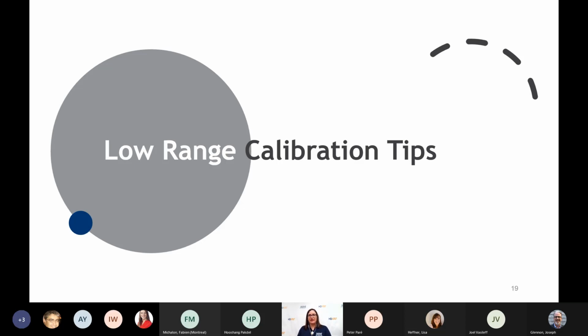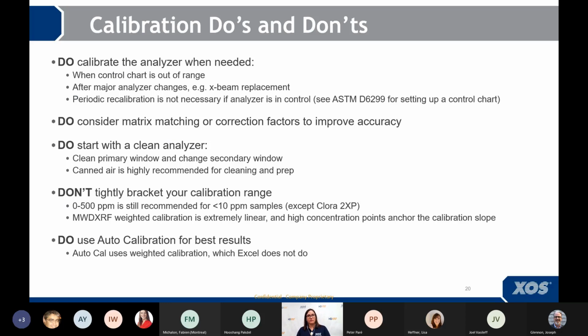First, we'll start off with our calibration do's and don'ts. Do calibrate the analyzer when it's needed. That's when your control chart is out of range. Some people like to calibrate also when you have major analyzer changes, such as an X-beam replacement. Some people like to calibrate on a fixed schedule, like once a year, but that's not necessary. It's not harmful, but it's not necessary. Really, the trigger for recalibration should be your control chart.